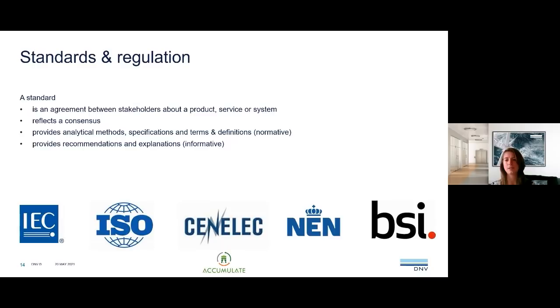There is a risk of limited clarity about regulation, and that's what we currently see within the European Union—a lot of local variation. It's a good initiative in the Netherlands that we try to make national regulations now, before it was really organized locally within different regions. There's a risk that regulation might change, so that later on you need to make adjustments to your battery storage system, which is a really expensive exercise. And there's a risk of overreaction in case of an incident, because if we're not capable of distinguishing the good systems from the bad, public perception changes, which we definitely want to avoid. So it's to the advantage of all of us to be open about safety, to be clear about safety, and to assure the safety of the storage system.